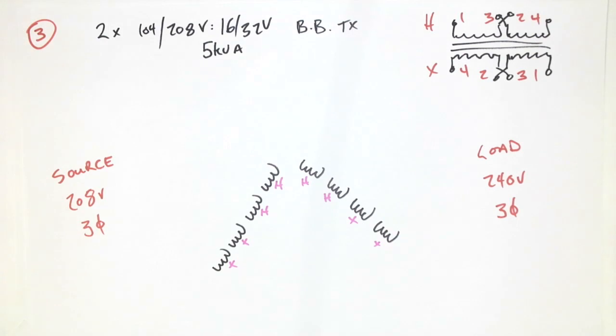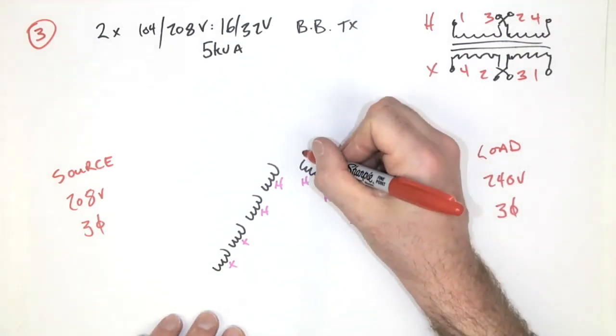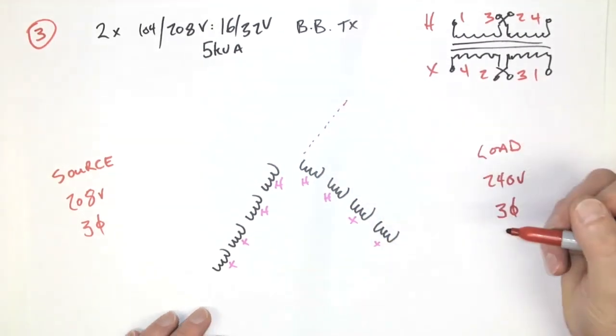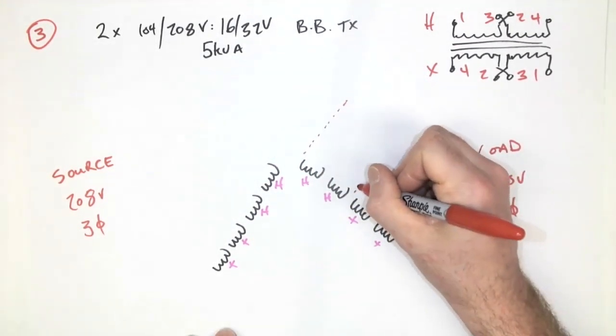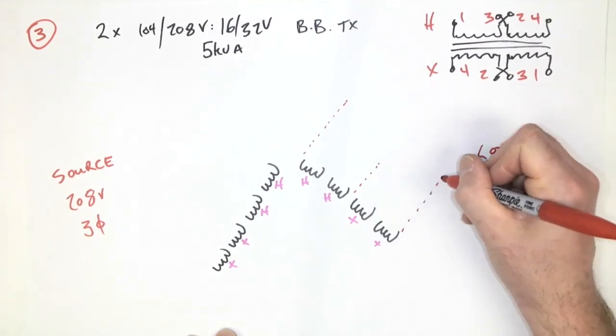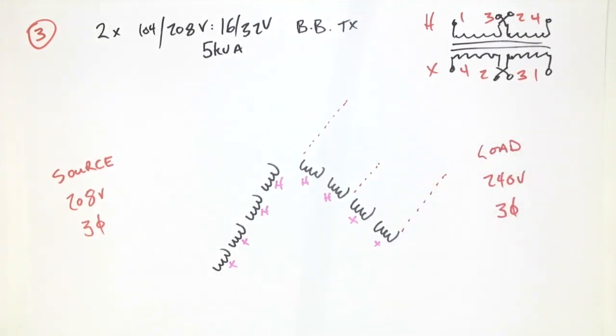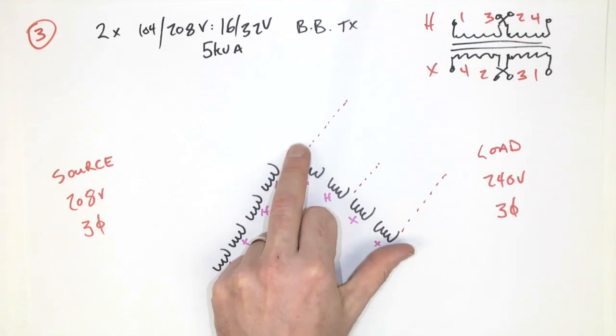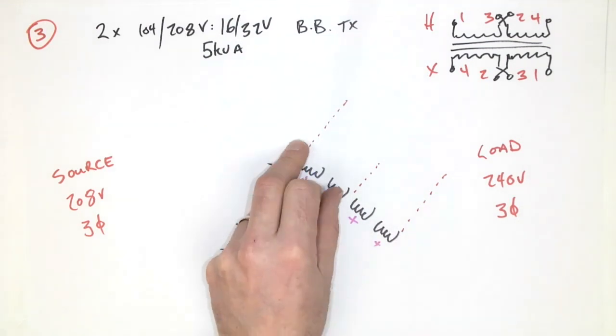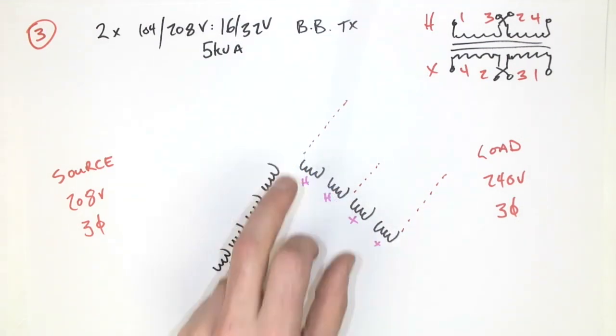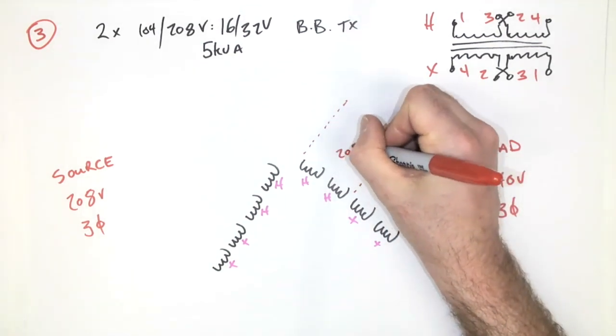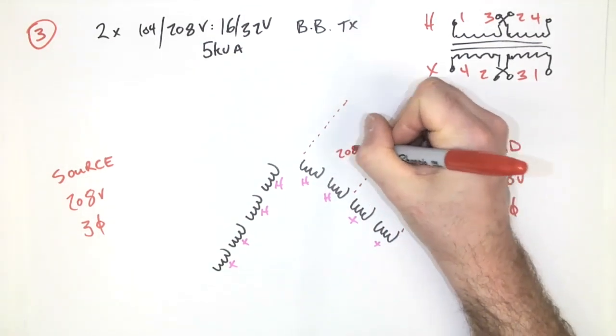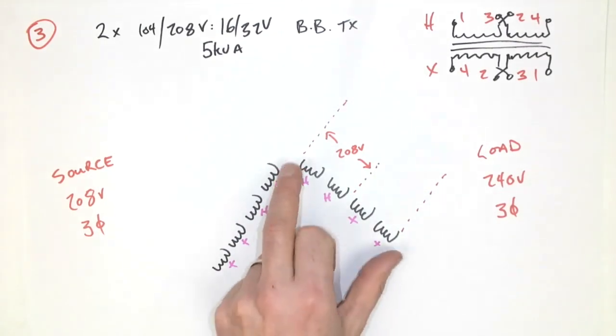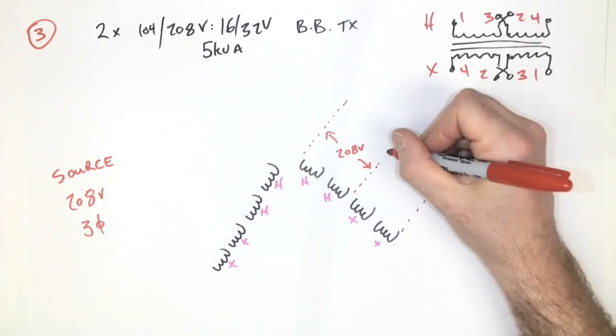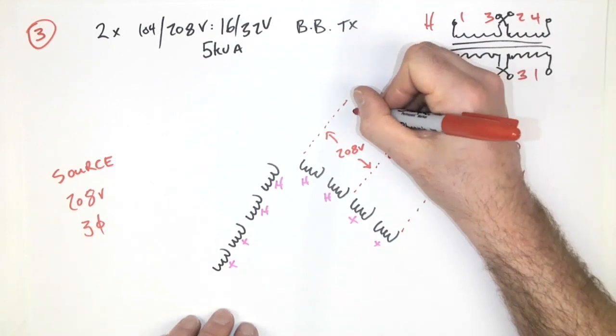I'm going to put the voltage that we require in much the same way that we did with the Y connection. So I have a lower voltage and a higher voltage. The lower voltage is 208. So 208 volts I need present here and here. The high voltage is here, and the voltage I need for that one is 240 volt.